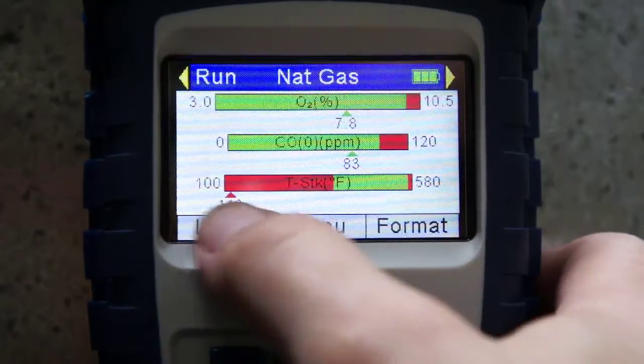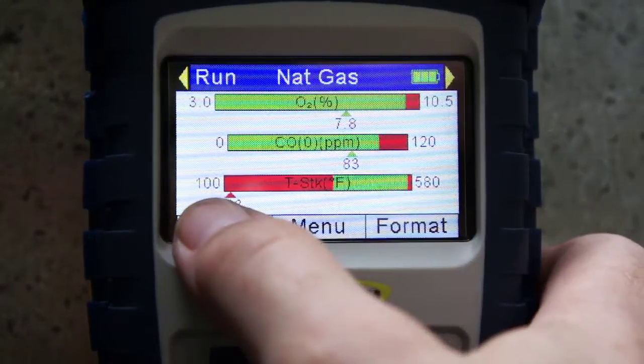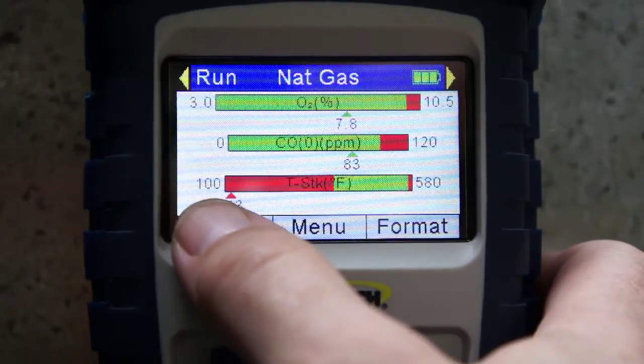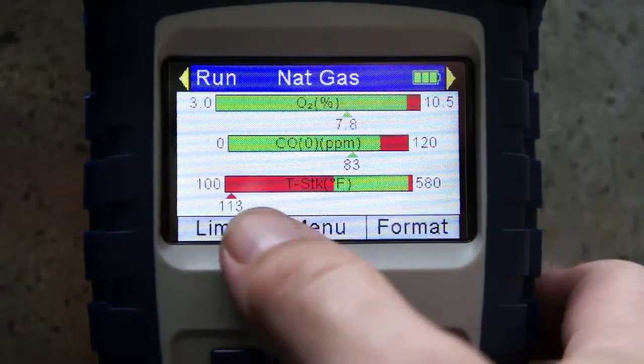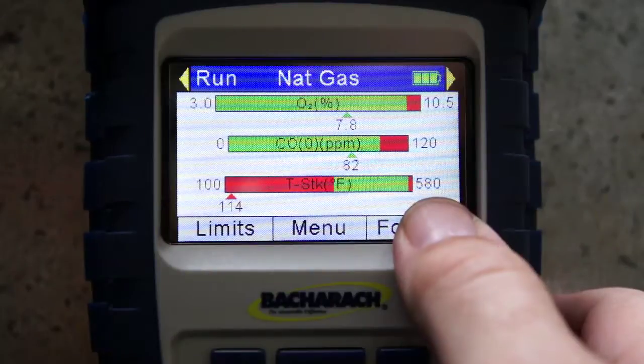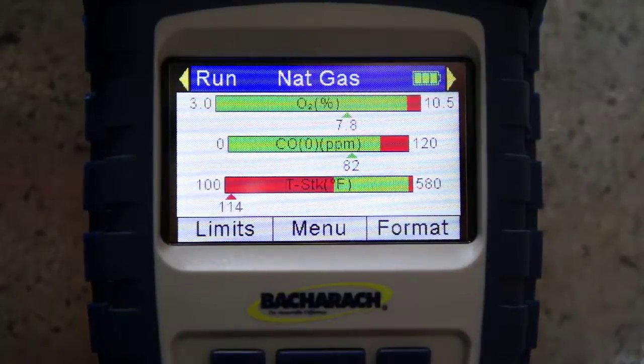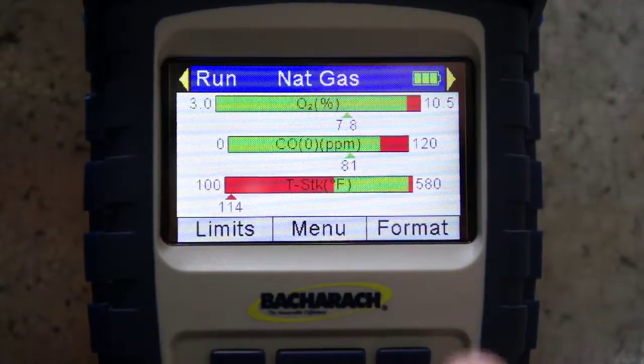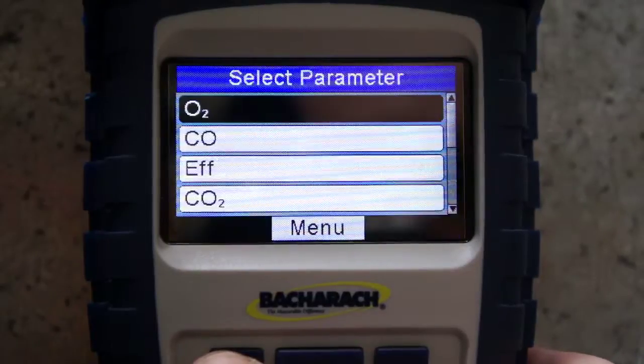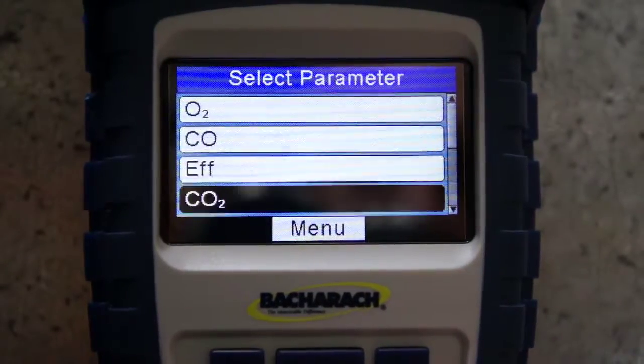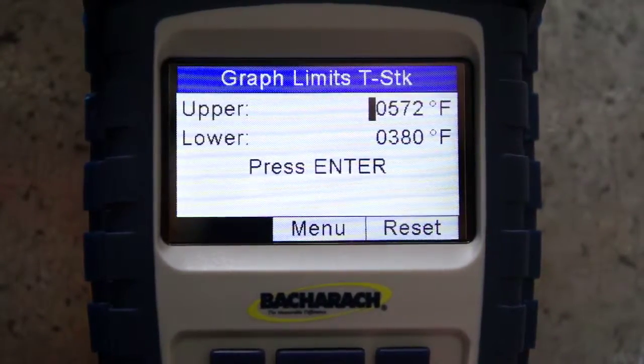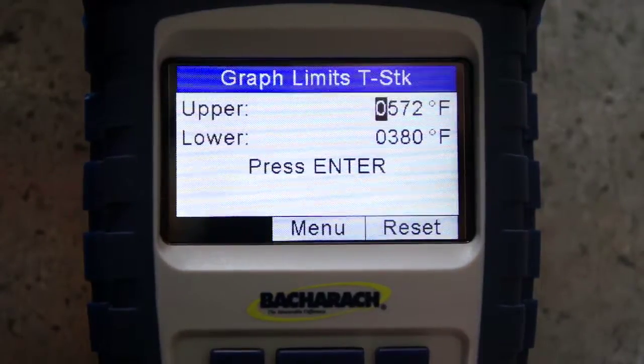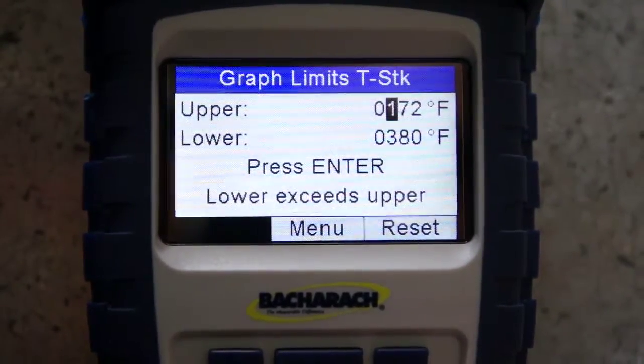Now, I want it maybe stack temperature. Well, you can see right here, for a 90 plus furnace, this is a problem because obviously it's not going to reach up in the 580 degree range. This is a condensing appliance, so we're going to have to lower that down. Well, maximum temperature we want to see on a 90 plus is about 120 degrees. So I'm going to change that upper limit here to 120.